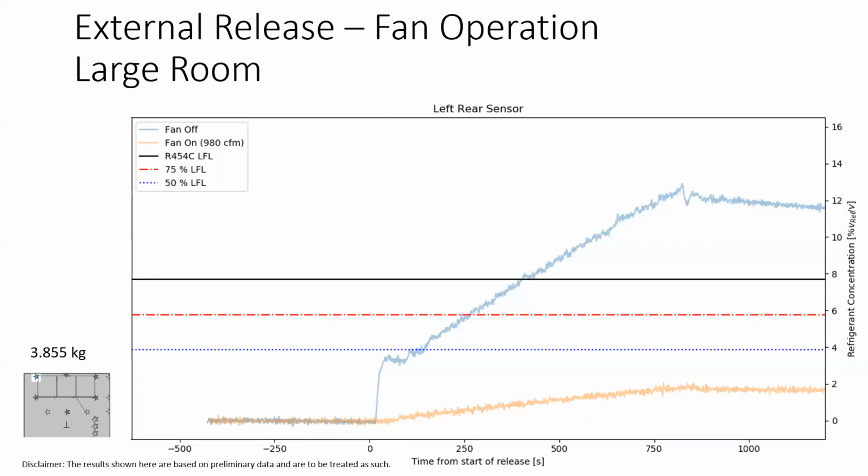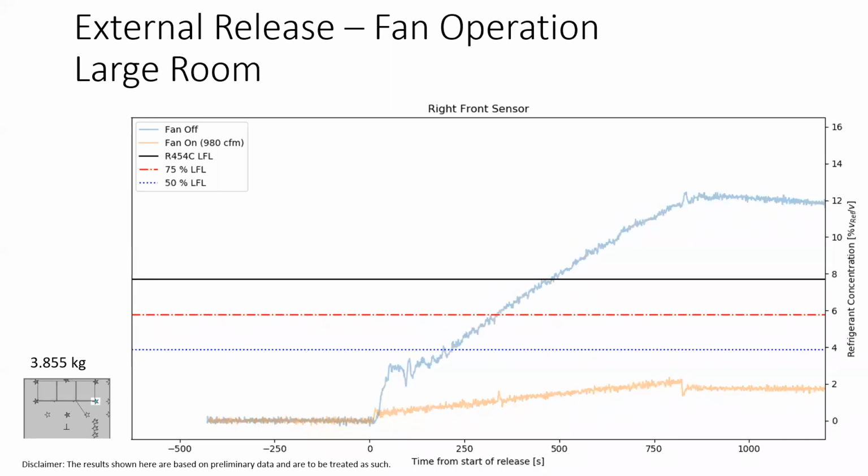But what we can see by going to the next slide is when we look at that sensor location that's closest to that leak point, we really don't see significant difference. There are slightly different concentrations, but as far as the gross outcomes of the test, whether it would be considered to comply or not comply with the requirements of the standard, we really don't see a difference based on that sensor location as opposed to the airflow being the dominating factor. So in summary, if we go to the next slide.